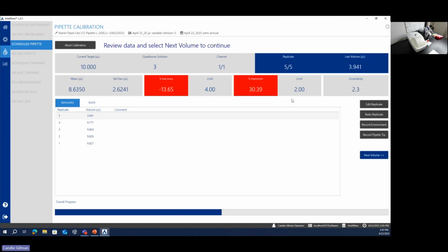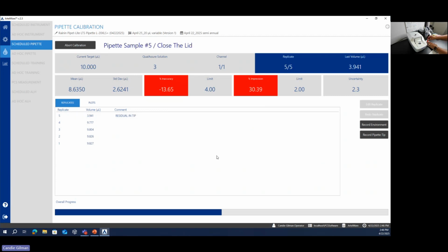All right, so those boxes have just turned from green to red. So I intentionally didn't dispense all of my solution on that very last replicate. So the system has the ability to enable you to redo replicates. Maybe you had a gross error like the one that I just had. And so once you've dispensed all of the volumes for a particular data set, you have the ability to go back and select a data point in that grid and click in this redo replicate box. The moment you do that, the system is going to force you to enter a comment. So I'm going to say residual in tip. And I'll go ahead and click OK. And then the system opens again. It wants me to go ahead and make another 10 microliter dispense. So I'll go ahead and do that.